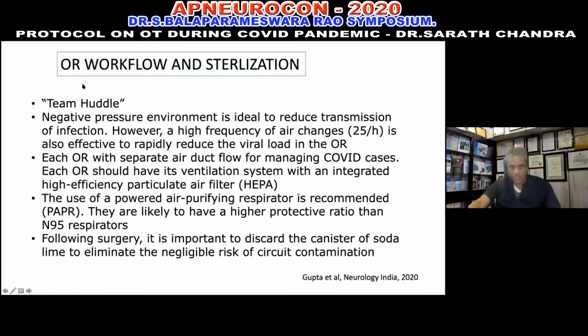Now it's important to optimize the OT workflow. So every day morning it's important to do a team huddle. But by team huddle, I don't mean that physically everybody gets together or touches each other, but to plan out how the OT is to be streamlined. It is very important to create a negative pressure environment, and it is important to ensure that every OT has a separate air duct flow. So one has to speak to the engineers to ensure that there's a separate air duct flow.